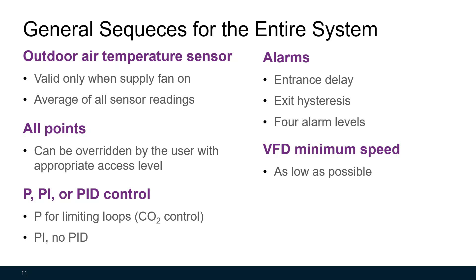For alarms, there are several ways to eliminate false alarms, and four alarm levels are defined in this guideline. For variable frequency drive (VFD) minimum speed, this guideline recommends as low as possible. Some VFD manufacturers may recommend at least 20% or 12 Hz as the minimum speed, but this guideline suggests you can go lower than that, down to even a few Hz.